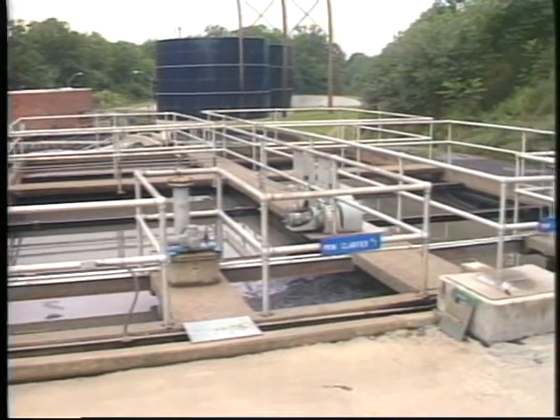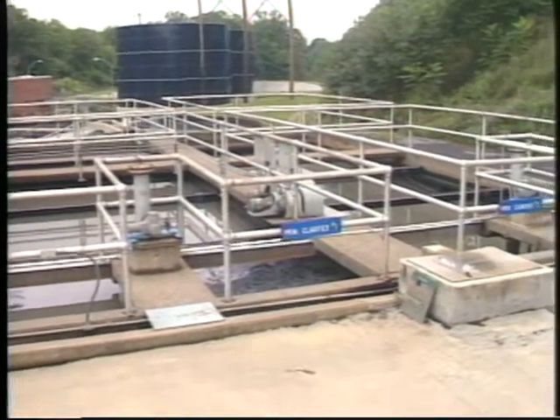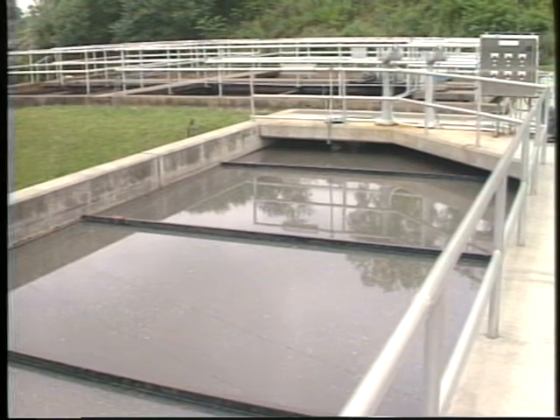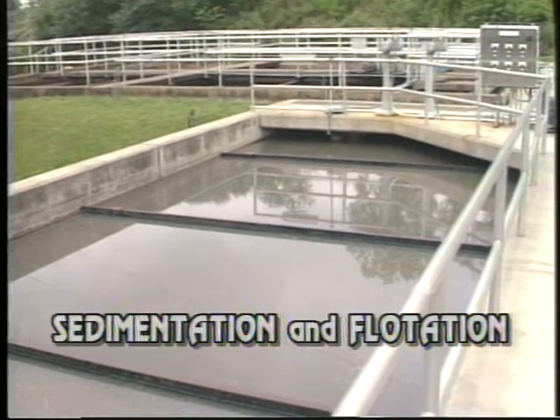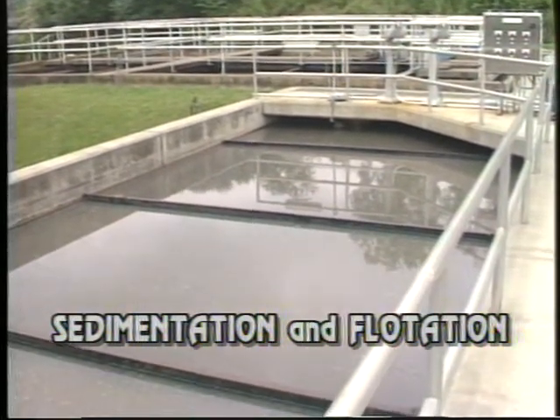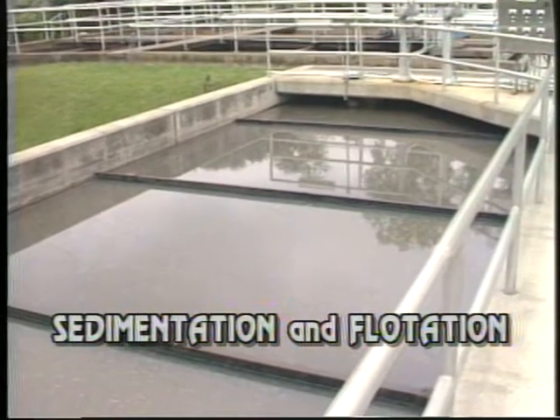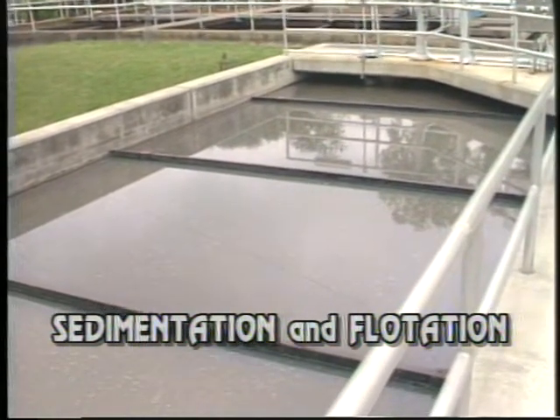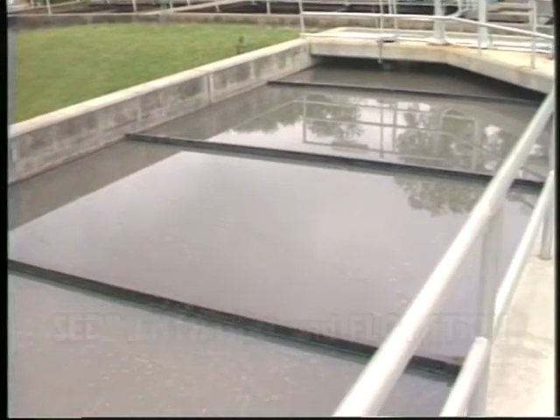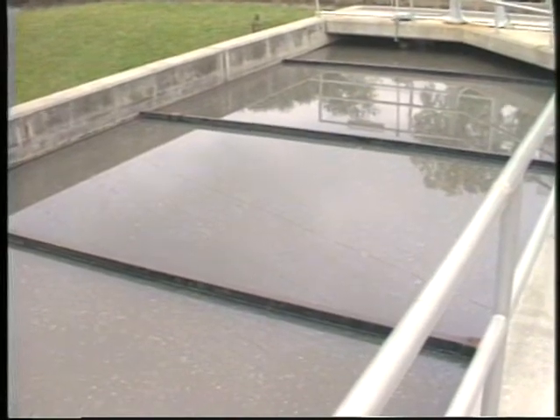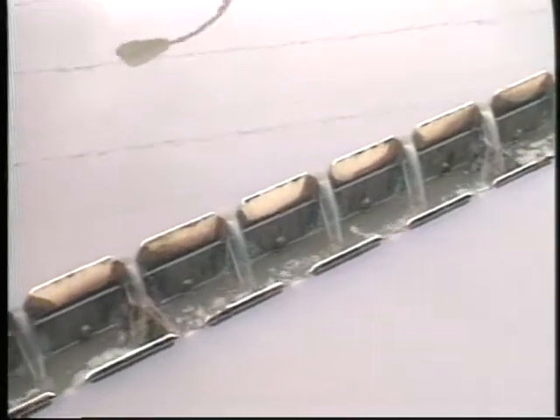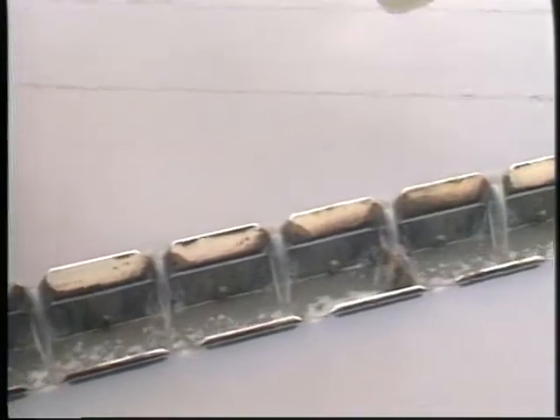The main job of the sedimentation and flotation process is to remove settleable and floatable solids by greatly slowing the velocity of the wastewater while providing a placid environment where many solids will either settle or float. After the solids settle out or float to the surface, the clarified wastewater flows over the effluent weirs onto the next stage of the treatment process.